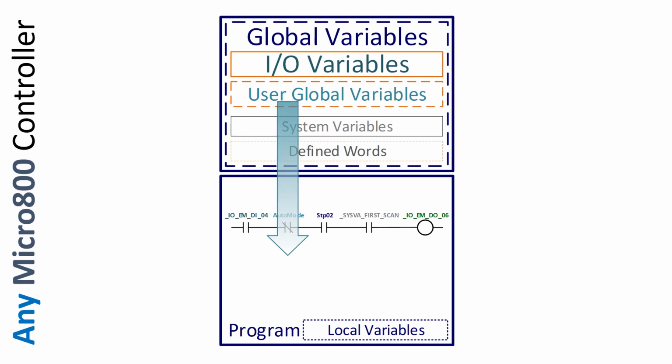The second instruction, a reverse contact, true if off, reads the on-off state of the memory location that it is addressing. If that bit is off, then the instruction is true. Consequently, if that memory location is on, then the instruction is false. So here's where I like to point out why I call these true if on, true if off. It just cuts right to the chase. Reverse and, direct contact, reverse contact just don't do it for me personally.